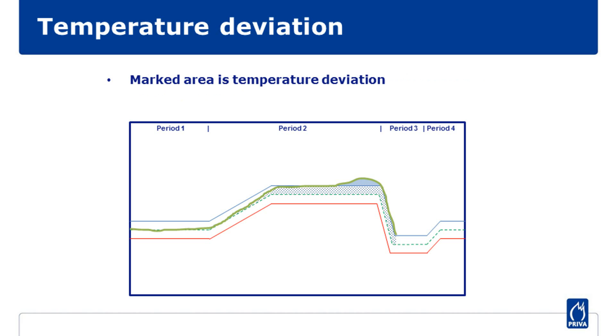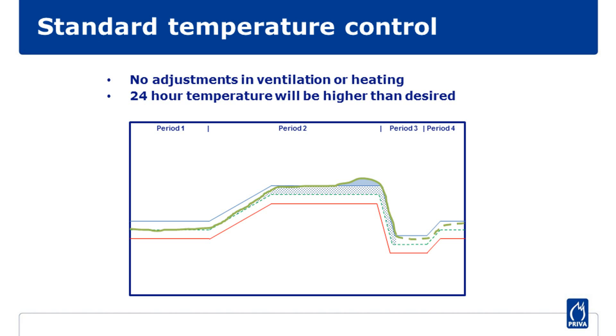Because the expected temperature is what I want to realise to achieve my 24-hour temperature. In other words, the area between the temperature measurement and the expected temperature is the temperature deviation. When I do not make an adjustment, the temperature in the glasshouse will be controlled on the basis of the ventilation and heating strategy. The graph shows an example of this with a dotted line. This means that there is a large part of the day the temperature is above the expected temperature, and the 24-hour temperature therefore becomes higher than desired.